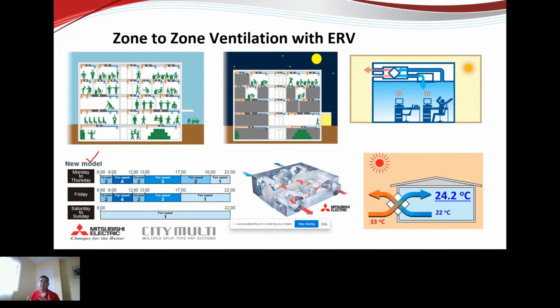And on top of the zone-to-zone ventilation, we also introduced an energy recovery ventilator to the space. So what it does is, let's say I am using electricity to cool my room air down to 22 degrees C, because outside is 33 degrees C. But without an ERV, I'm just dumping my 22 degrees C air directly outside, and I also introduce 33 degrees C air inside. I need to bring that 33 degrees C back into cold temperature, right? But in the case of an energy recovery ventilator, I will be able to use my exhaust air to cool the outside air. So instead of cooling the air from 33C to 22C, I really just need to cool it to 22 degrees C from 24.